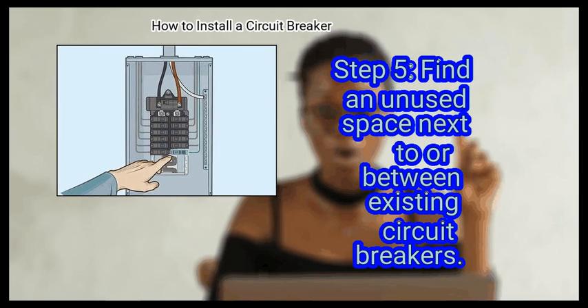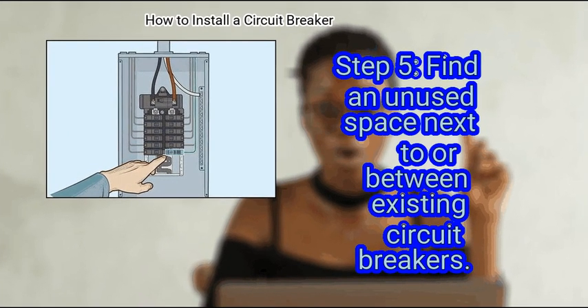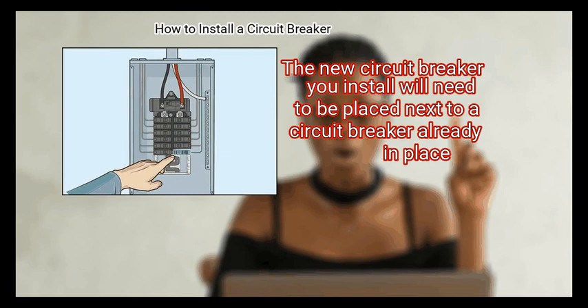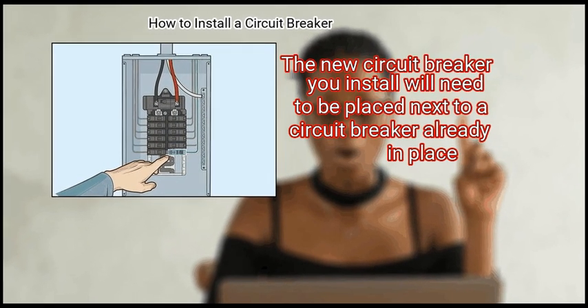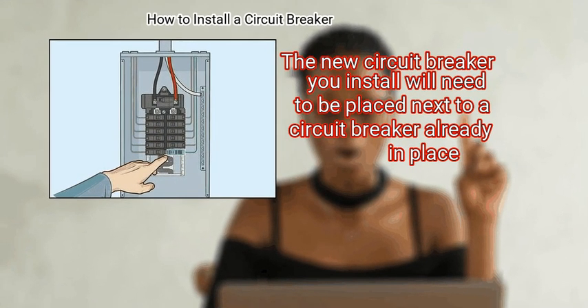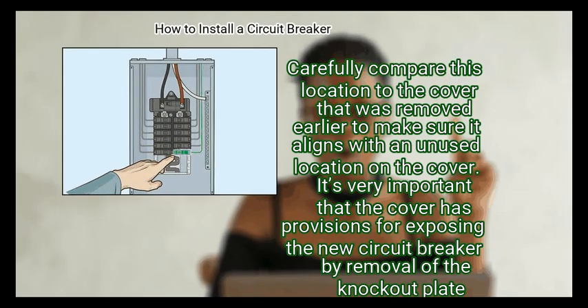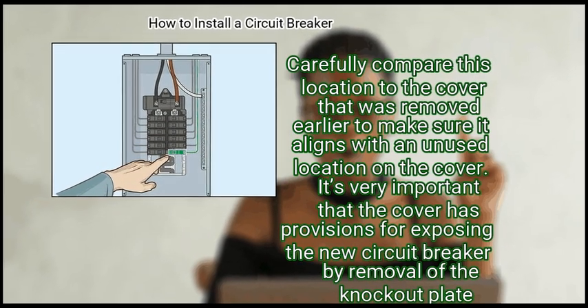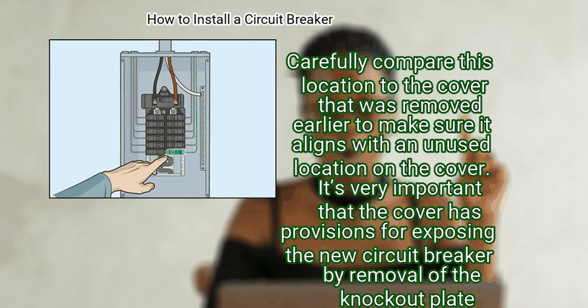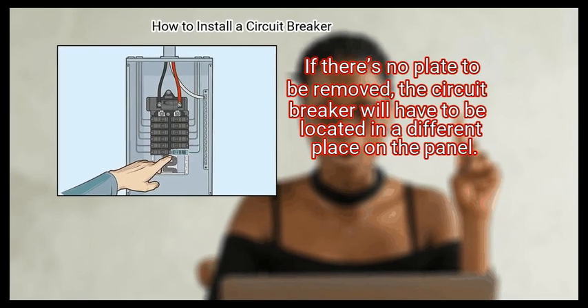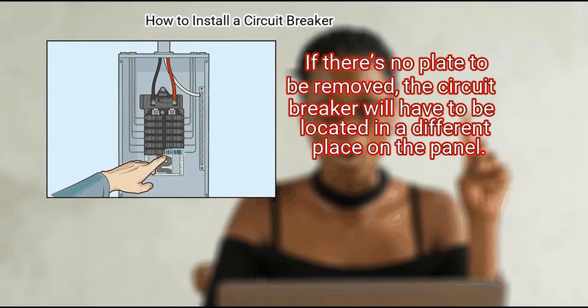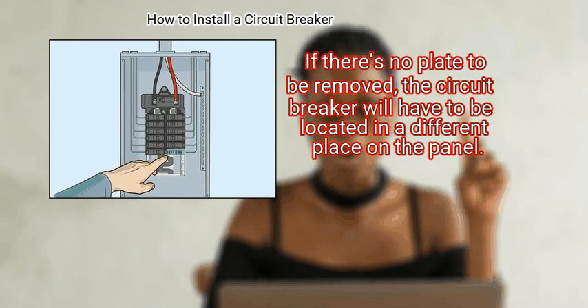Finally, find an unused space next to or between existing circuit breakers. The new circuit breaker you install will need to be placed next to a circuit breaker already in place. Carefully compare this location to the cover that was removed earlier to make sure it aligns with an unused location on the cover. It's very important that the cover has provisions for exposing the new circuit breaker by removal of the knockout plate. If there's no plate to be removed, the circuit breaker will have to be located in a different place on the panel.